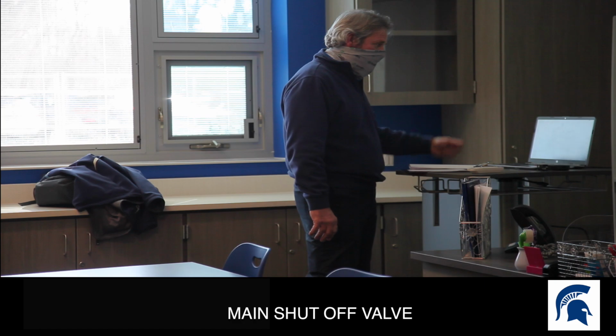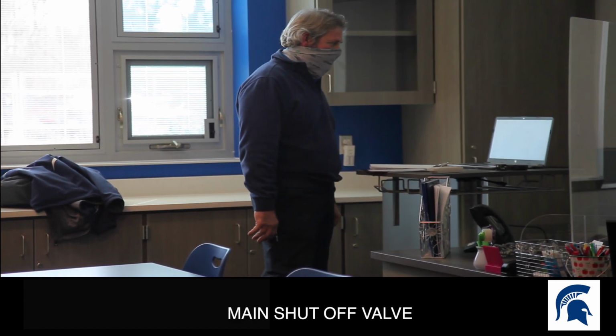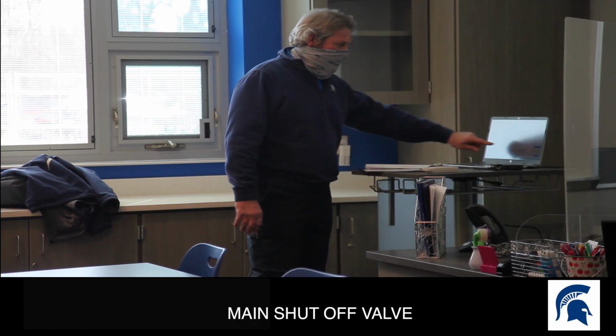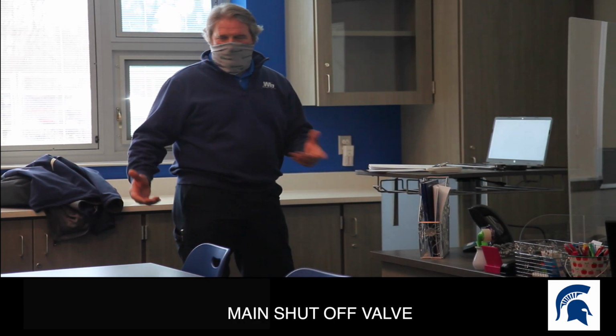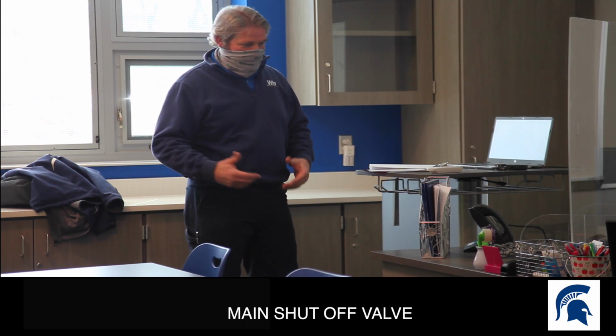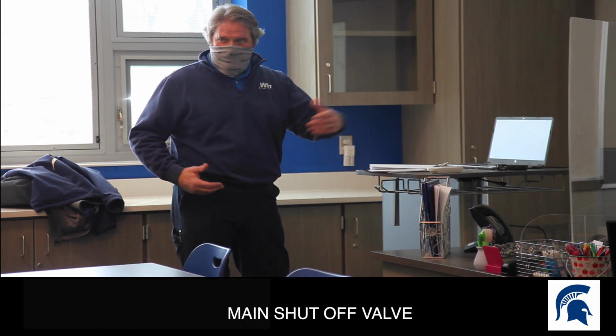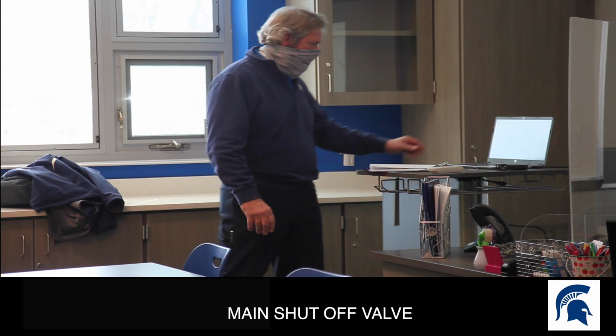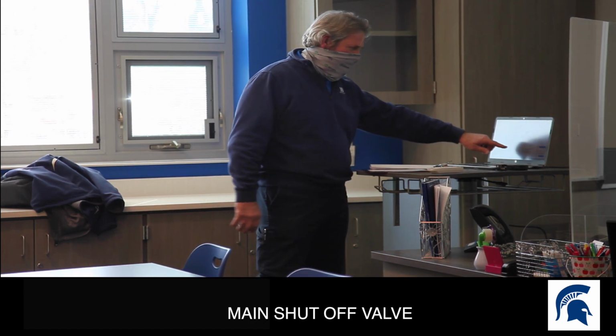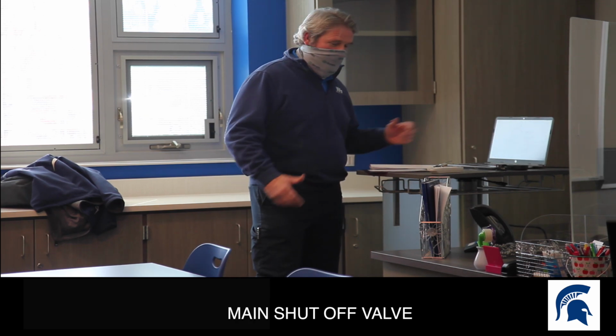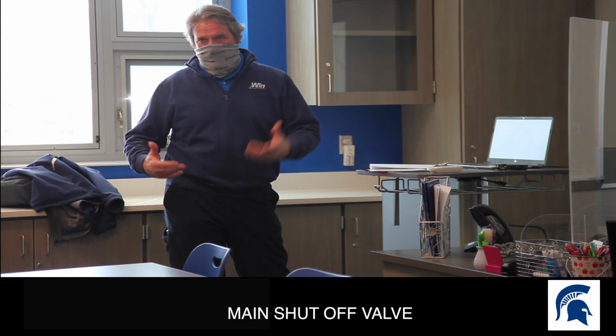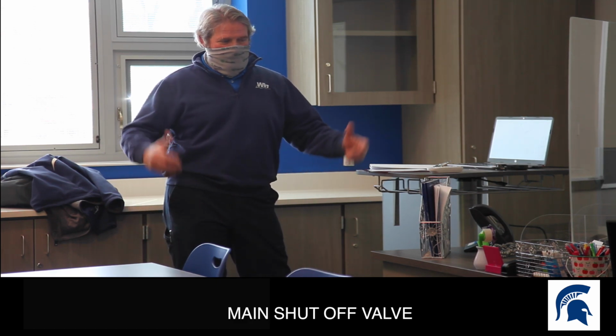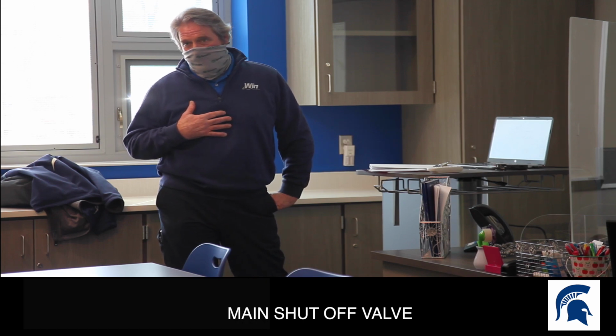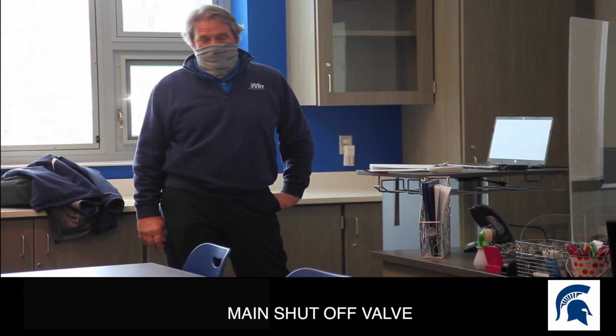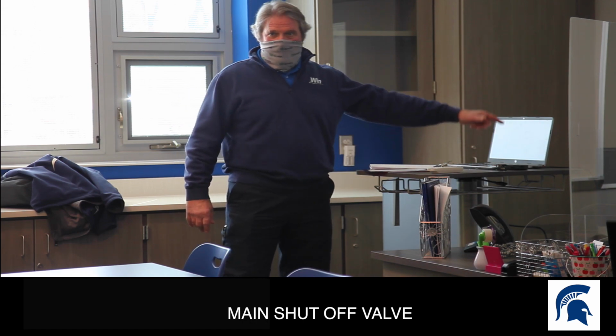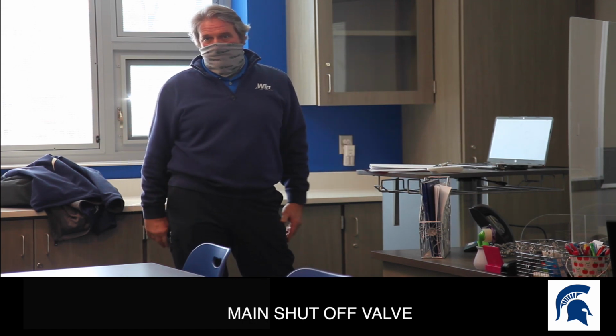checklist, and then every 6 months you want to check for leaks. It's basically normal maintenance: walking around visualizing no leaks, no extra water sitting here, no smelly gas or anything like that. T&P, again, they want you to check that. It's very important as well. And water chemistry, you take a sample, you send it out to a lab, and they'll tell you where you're at. I don't know of many people who do that. That's up to you guys if you want to do that. They advise it because that's going to help the whole system run perfect, if you may.